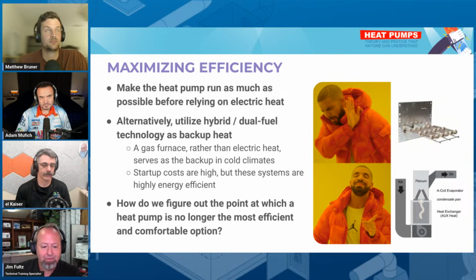So yeah, just to summarize everything, typically a heat pump's always going to be more efficient. It seems like the reason homeowners switch over is that feeling of cold air blowing on people. So finding ways to set customer expectations and talk to people about why that's happening, and set up controls correctly so that you're still maintaining efficiency while providing comfort. Yeah, I think controls is probably one of the biggest reasons, but comfort is always a concern. If we set the controls up right, then we can keep them comfortable and have good efficiency.